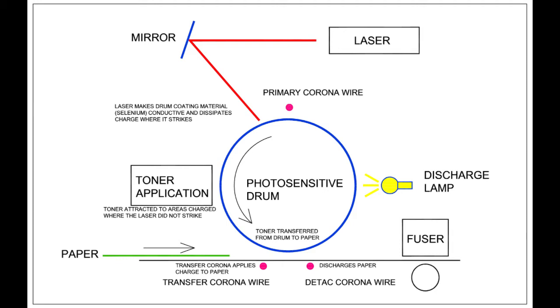That's what I got from one source, but I guess different manufacturers and different sources have different views on this, and positive and negative different views on this again. As it's charged up, the laser then - and if you look at the direction of rotation, it's anti-clockwise - the laser hits against a mirror, comes on and off, and scans across the surface of the drum.